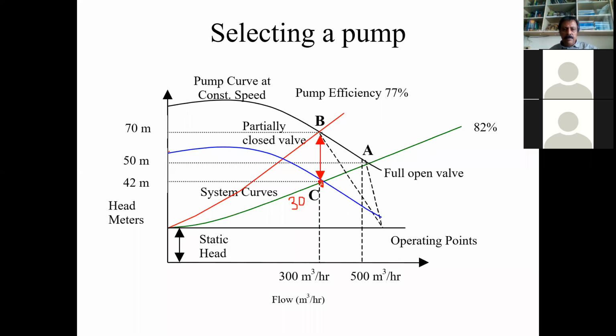The other option: sometimes you want 300, sometimes you want 400, sometimes you want 200. So these kinds of fluctuations or variations are there in the process. Then what are the options? Since there is a varying requirement, the ideal option will be to go in for a variable frequency drive, which will have many speeds. The pump will operate at different speeds, and for each speed, the pump characteristic curves will be like this. So this is at full speed, reduced speed, further reduced speed, and another reduction in speed. As you see, when you reduce the speed, it's almost like operating a smaller pump. So we get the blue pump also by reducing the speed of the pump.